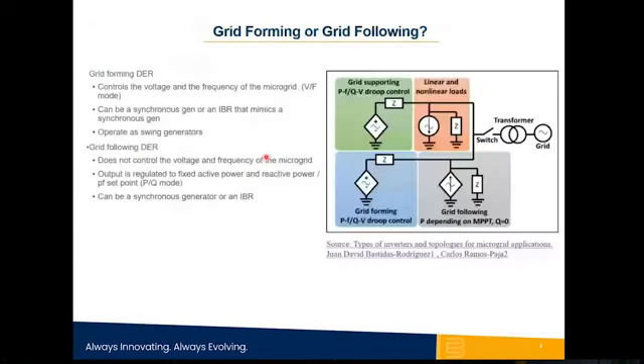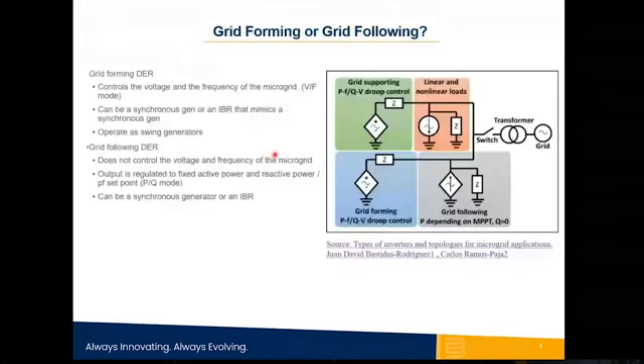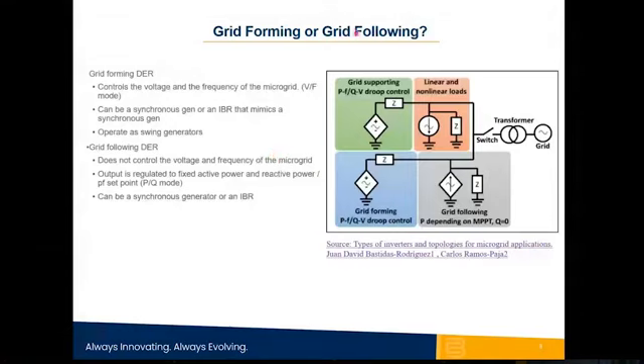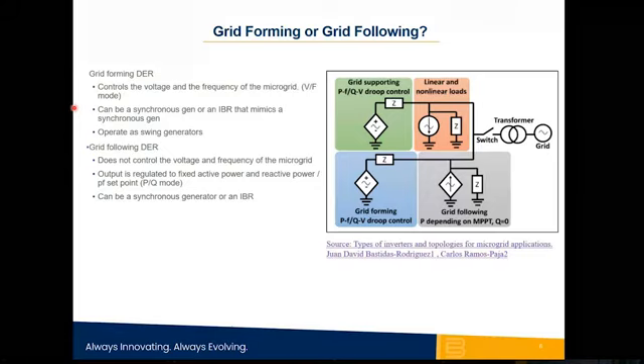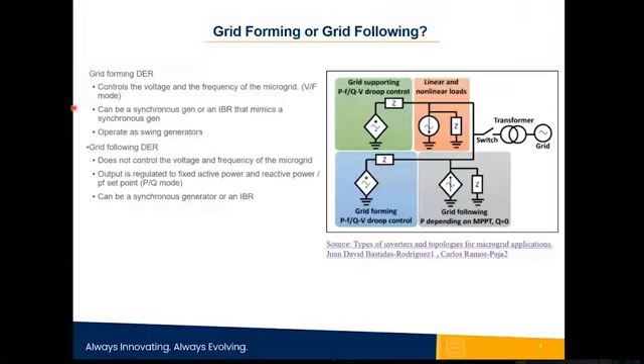Another important concept to understand when it comes to microgrids is grid forming versus grid following. So let us define what a grid forming distributed energy resource is and what a grid following distributed energy resource is. Grid forming means that that resource controls the voltage and the frequency of the microgrid, meaning VF mode. An example of that is island load share. If I have 3 generators paralleled together and they are all in island load share, then each of these generators will be responsible for contributing towards the voltage and frequency stability of that small system, that local system.